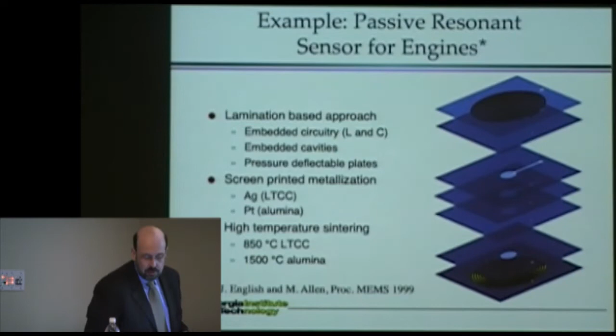We built it not out of silicon, but instead out of ceramic. The particular ceramic that we used was aluminum oxide, either low temperature co-fired with glass or alumina. Using this green sheet technology, which you may be familiar with, coupled with lamination, we were able to build up multiple sheets consisting of coils on the top and bottom, and cavities that allowed us to create the encapsulated cavity for this device to operate. The way this is fabricated is these individual sheets are all brought together, laminated and co-fired, and you wind up with a block of ceramic encapsulating the cavity with all of the coils and so on fabricated inside.